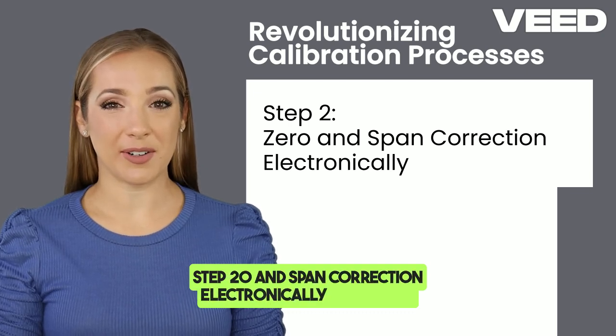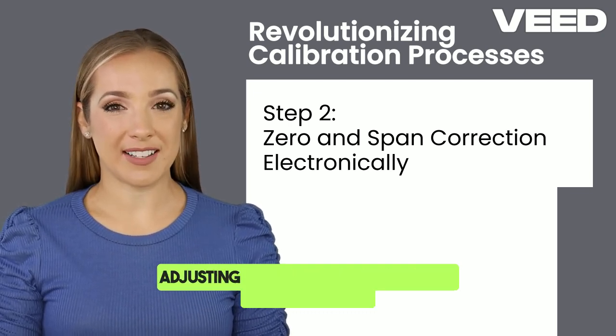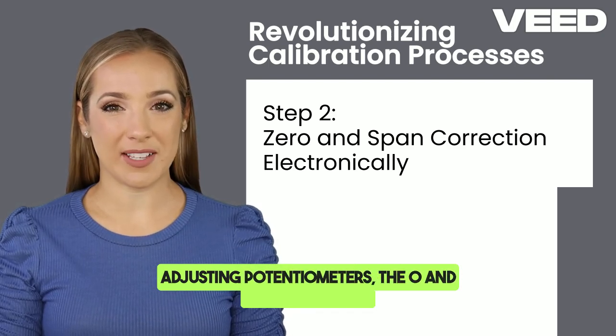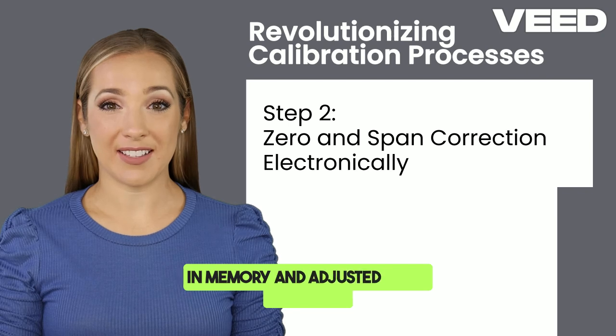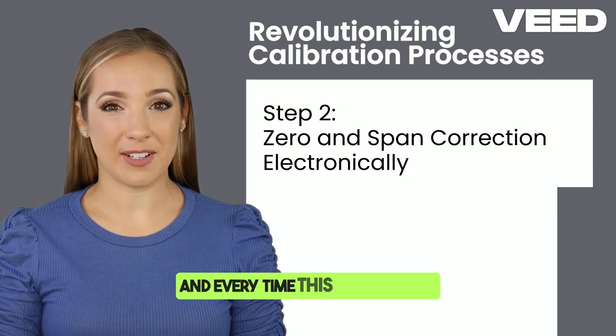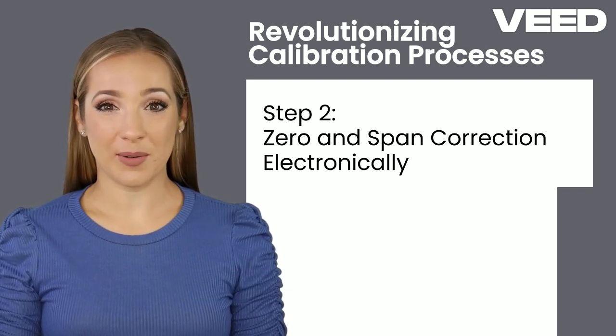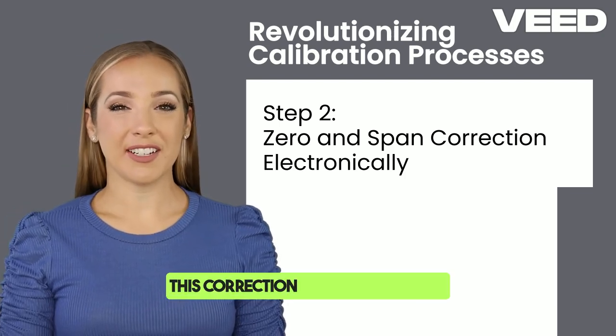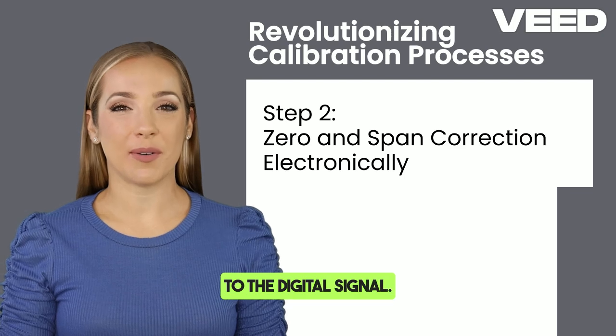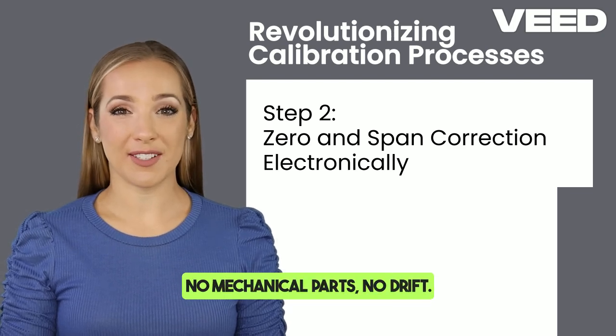Step 2. Zero and span correction electronically. Instead of adjusting potentiometers, the zero and span are stored in memory and adjusted using software, and every time this stored value is subtracted from the raw value. This correction is applied directly to the digital signal. No mechanical parts, no drift.